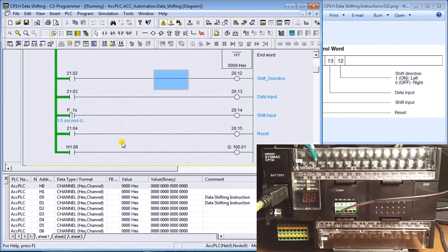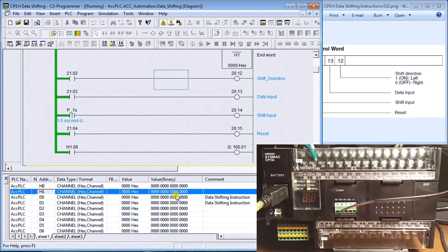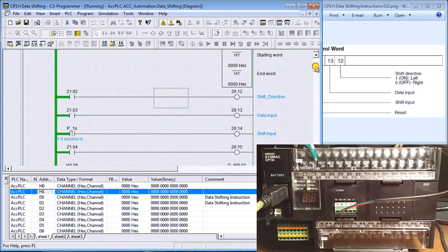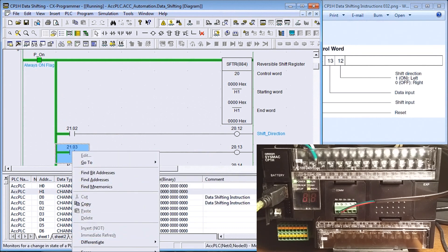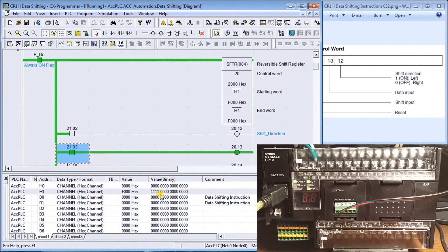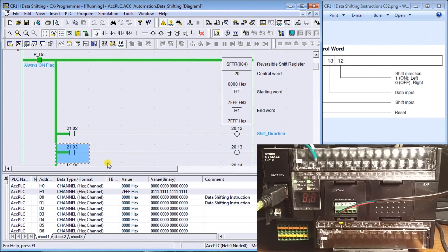The shifting input is at 20.14, and reset is at 21.04, which clears the register to zero. H1.08 — the eighth bit — when it turns on will turn on the output. Looking at my H register here, when that bit turns on the output turns on. With direction set and data input on, the bit turns on, the output turns on. I can then make it send the other way, shifting everything to the right, and we can toggle the direction to shift it back.